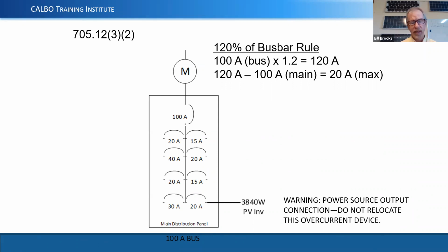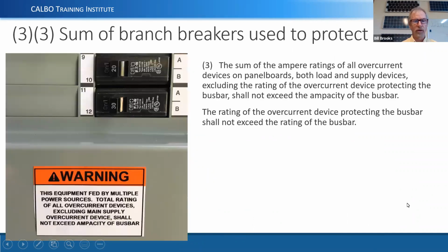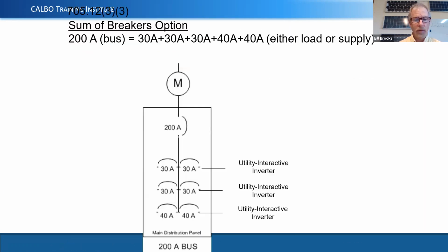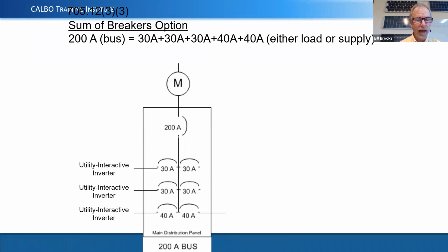Now, with the 200 amp service, obviously everything doubles, and so the 7.6 kilowatt inverter is by far the most common inverter sold in the United States, and it has this do not relocate the overcurrent device setup. However, the sum of the branch breakers is going to be the rule that we're going to use most often moving forward, particularly with our AC output energy storage systems. And we have to do it that way because we just don't have the capacity to do it with the 120% rule. And so what we're dealing with here is, let's say we have a 200 amp bus panel here. We could have a combination of loads and interactive inverters, and as long as the sum of those breakers is not greater than the bus bar rating, we're okay.